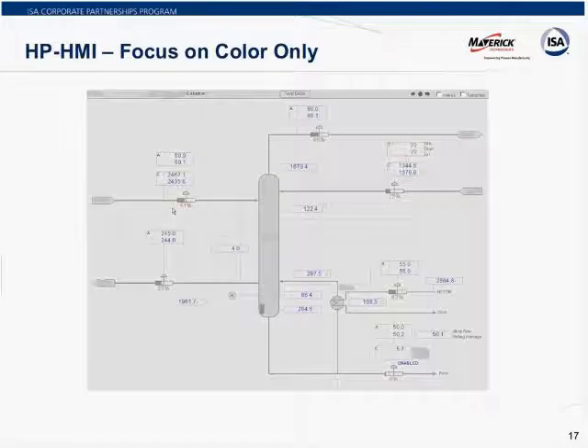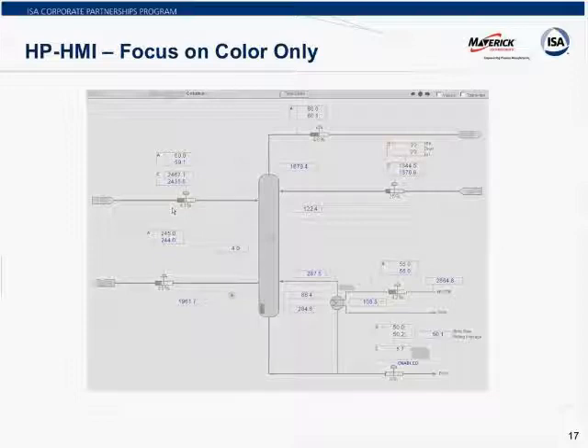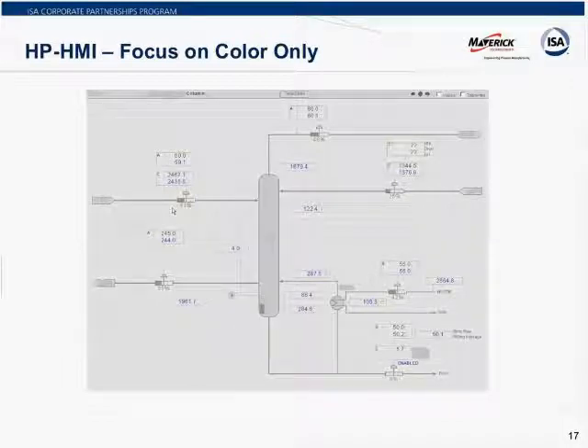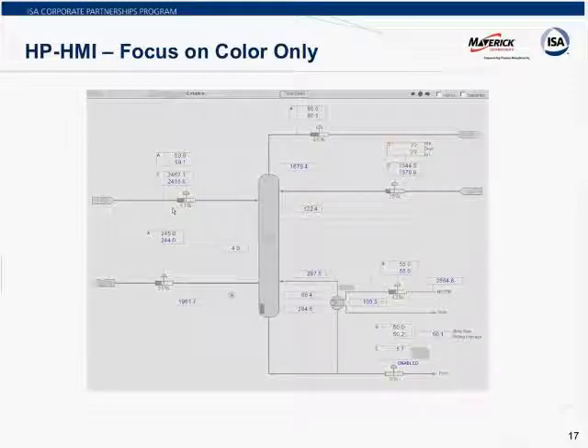Just as another example of things going way overboard — this is an actual example of a standard from a pretty major facility and they took the washed-out look to a whole new level. As you can see, there are complaints from operations, and it was really based on readability and being able to actually just see the data. We talk about color and gray-on-gray and all those different things, but there are limits to that as well and it needs to be applied judiciously.